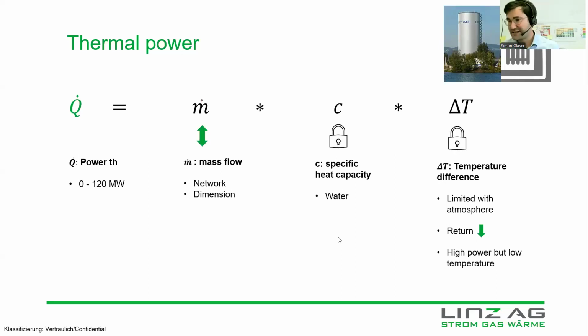The temperature difference is somehow locked because in our thermal open storage, we are limited by the atmosphere, so we cannot go above 100 degrees, but the return could go lower. That's a long story though—a lot of experts discuss how we'll get the district heating return lower. I won't focus on that now. The specific heat capacity will also likely remain water in our district heating systems in the coming years, so that's also locked somehow.